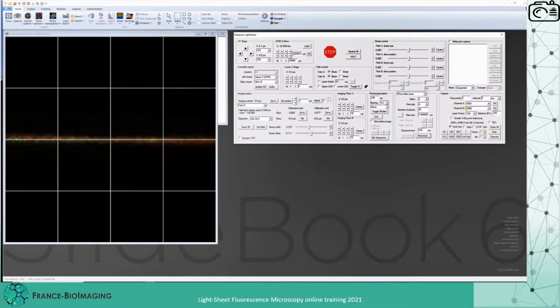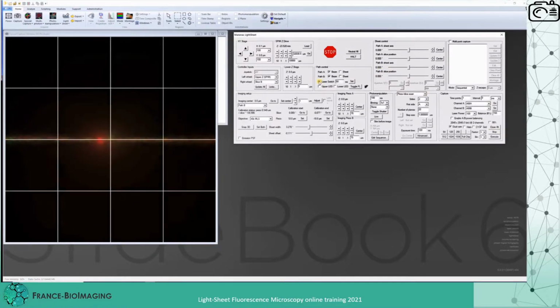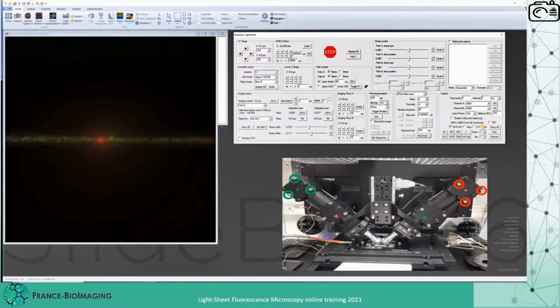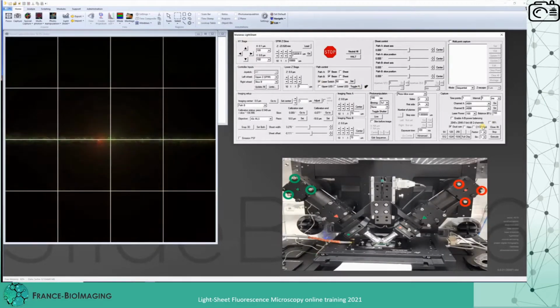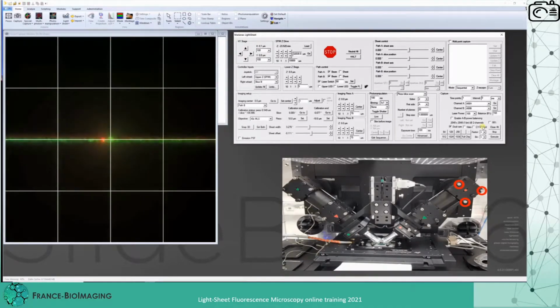Once this is done, we put the two beams back together using the slider again. We now need to check that the center of the illumination is the center of our camera. If this is not centered, we can adjust the tilting screws on the corresponding beam to align it properly.